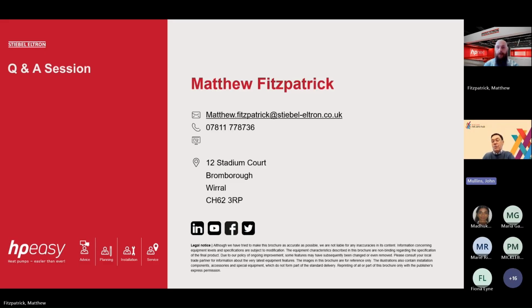Just to clarify, Matt, a few things that you made there was, for example, where a heat pump has to deliver two different temperatures, for example, to radiators and to underfloor. Is it not the case, just looking at your wiring diagram, that you are effectively blending some of the returning cool water into the low temperature circuit just to be able to get the right temperature?